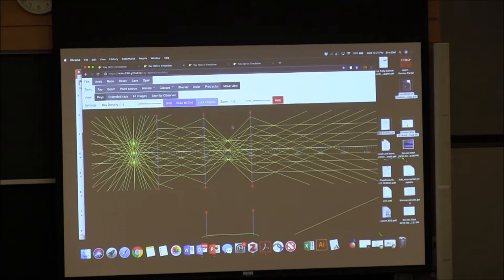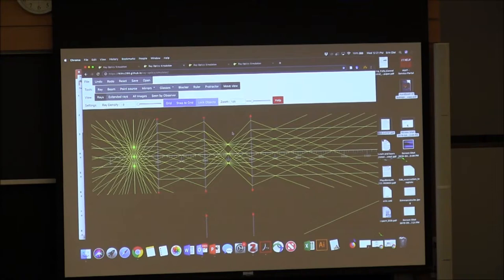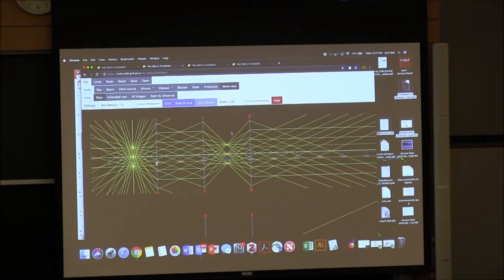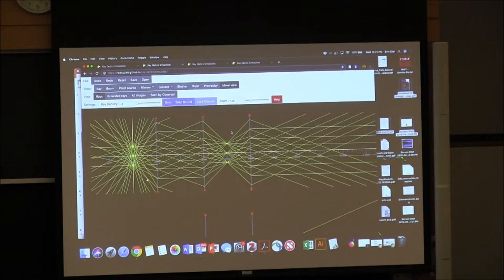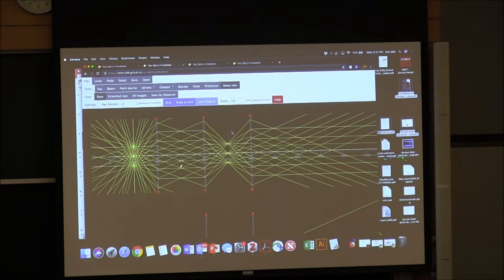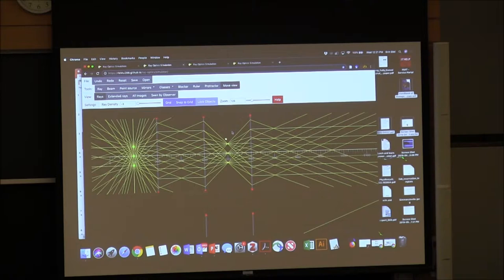Moving to a transmitted light microscope simulation with more lens elements: I still have my three point sources representing a lamp. There is a lens that produces parallel rays. Then a second lens refocuses this light — I now have an image of my filament — and a third lens gives parallel rays again. We talked about how this parallel-ray region gives nice even illumination, so we wouldn't want to put a sample where we have the filament imaged, because we'd be imaging the sample with the pattern of our light source.